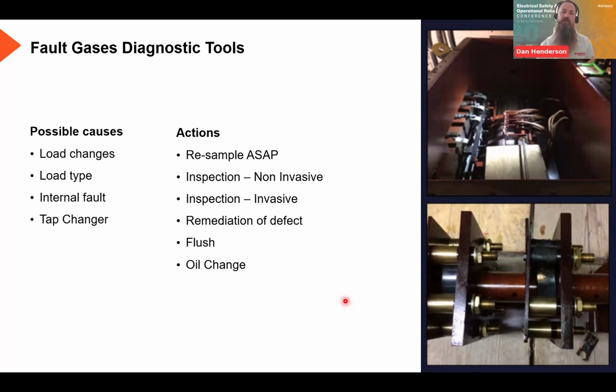And then there are options where we can potentially drain that oil out, flush it, and then conduct an oil change. But the biggest thing is, we have to fix the issue first. I've seen this so often, where people have fed back to me to say, we've had high DGA on this transformer, and we only changed the oil last year. This is common feedback that I get, and not to take anything away from anybody, but ultimately it's not the oil's fault. The oil's there, as Ryan said, as an insulator and as a cooling medium. It's there to help that asset operate. It's not the oil's fault that it's got dissolved gases increasing in there.